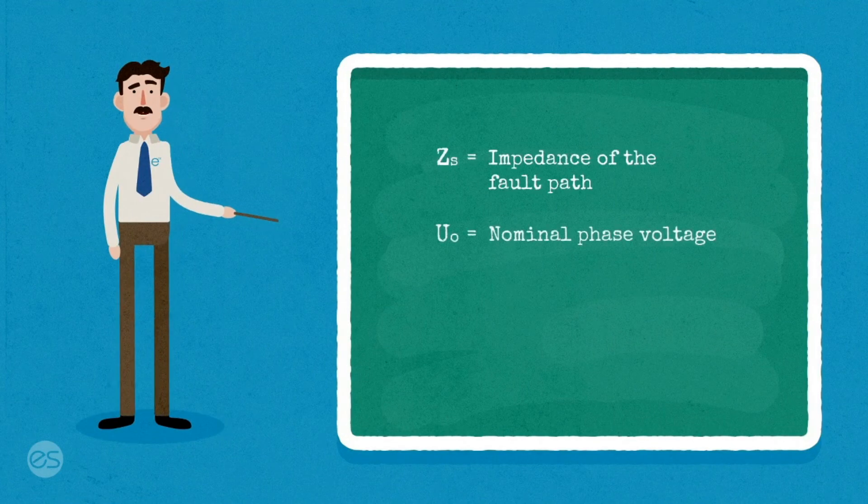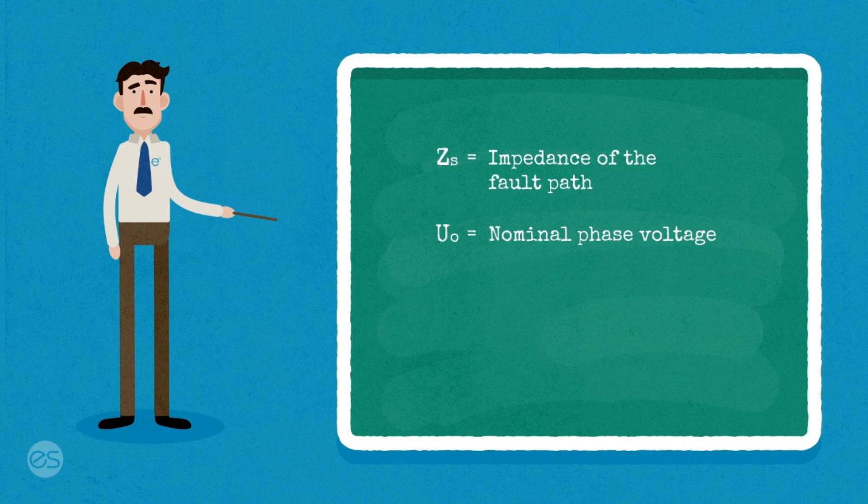AS3000 tells us that Zs equals nominal phase voltage, 230 volts, divided by prospective fault current.